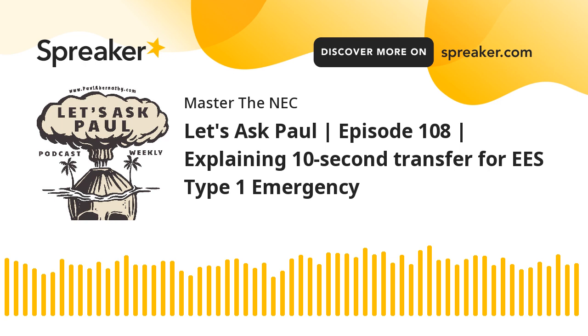Okay, good question. So I answered this question via email to make it clear. The references I gave were 517.32(B) and 517.26. So in my opinion, since the transfer switch is kind of the linchpin to the emergency system, and of course, being a healthcare facility, and this actually being part of the EES 1 part of it, which is the life safety branch, then for me, the 10-second requirement applies, right? It applies to the generator, and it applies to the transfer switch. Together, they have to work in tandem to bring power up within 10 seconds.